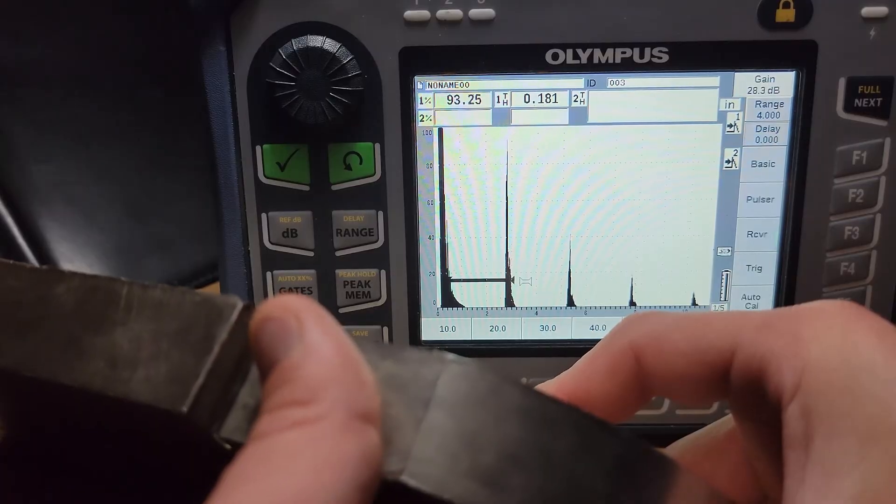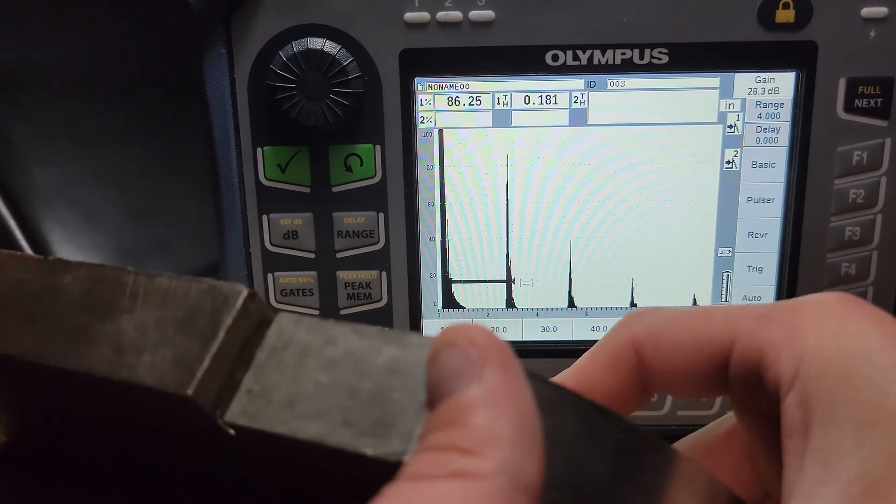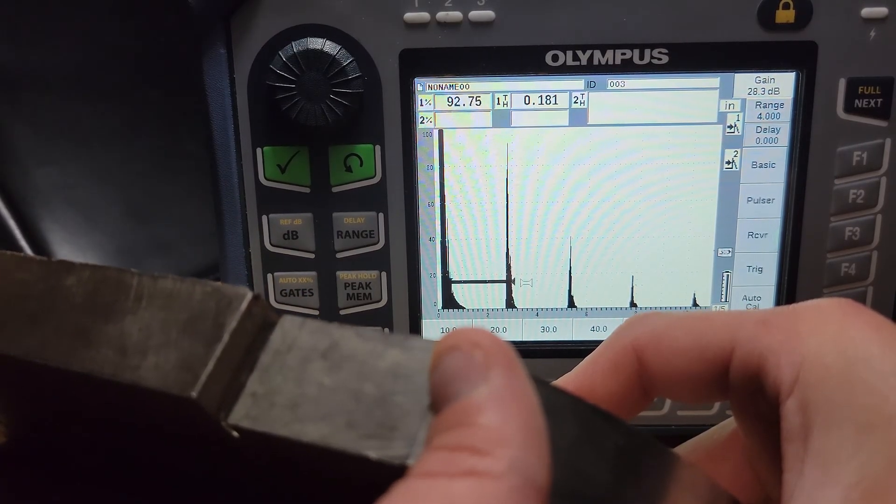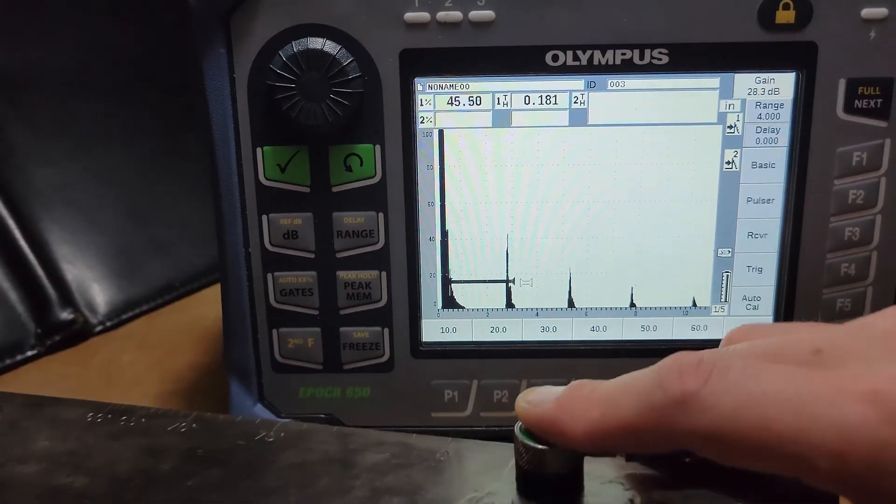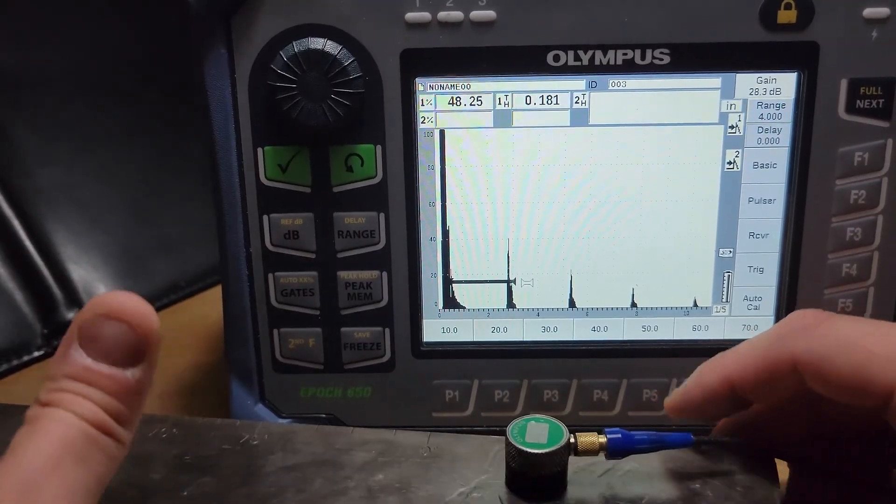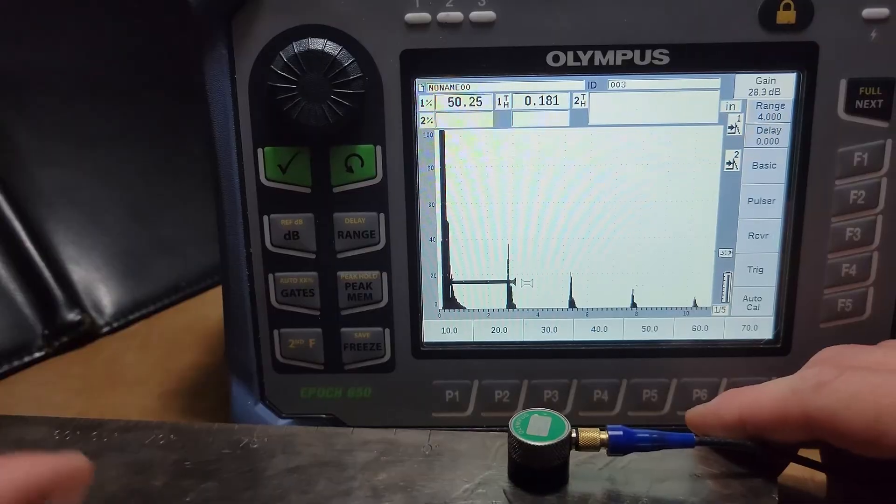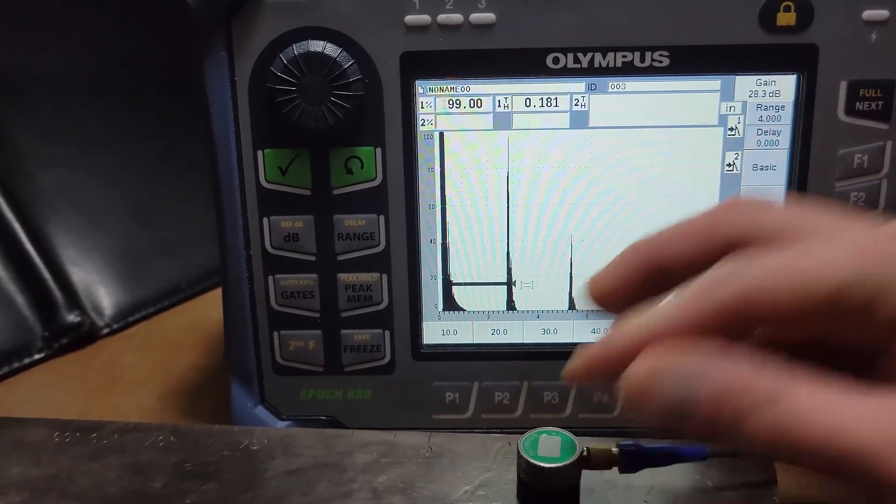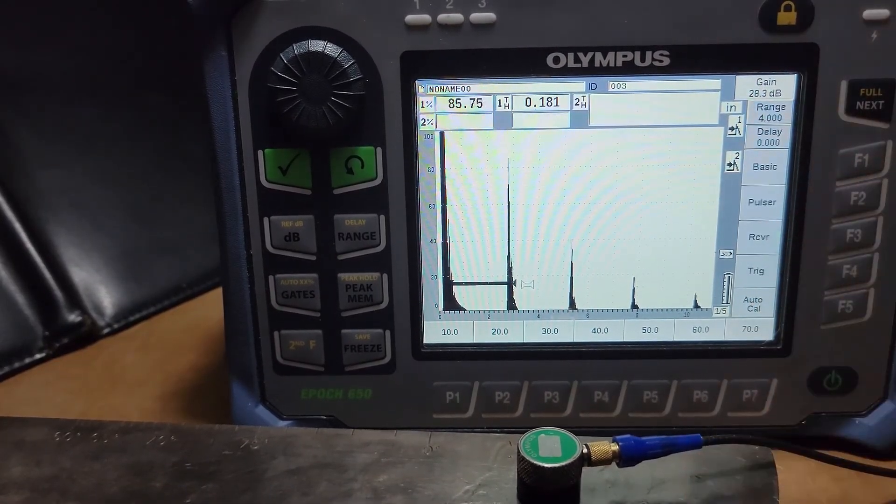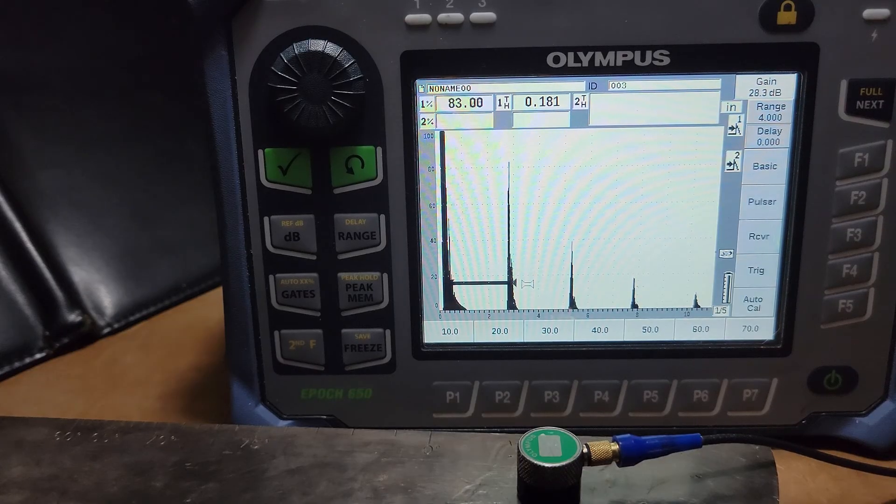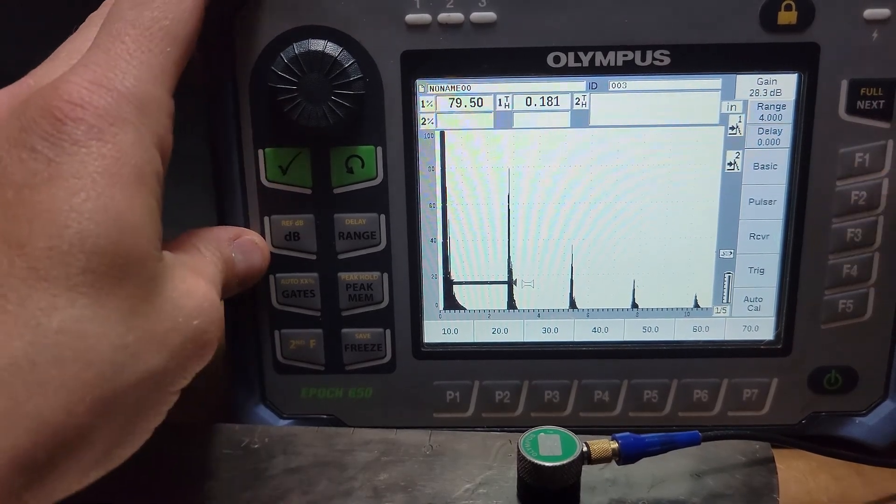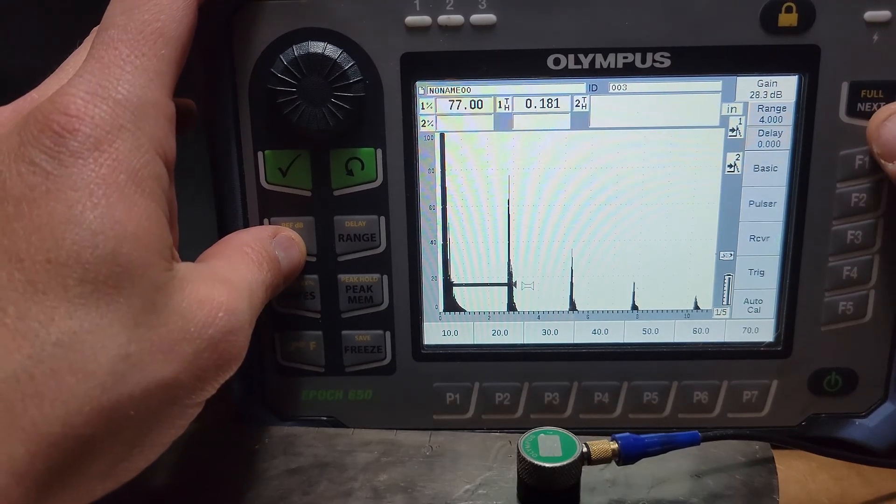Tap, tap, tap, tap, tap. Notice my right there, right there. And so that's one way that we can prove that hey, that is certainly a back wall signal and that is certainly going to be the thickness of my reference which in this case is one inch thick. We've got a one inch thick IIW block here.